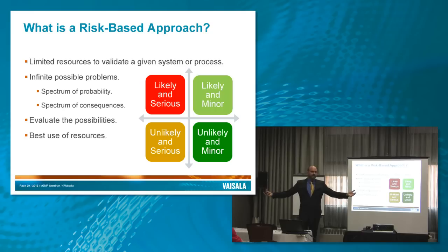To get that perfect detailed map of temperature distribution and dynamics in a space, we have maybe five or 16 loggers. We have to figure out how many to use, what we can do with what we have, how we look at the space, and pick out the problems that matter the most.